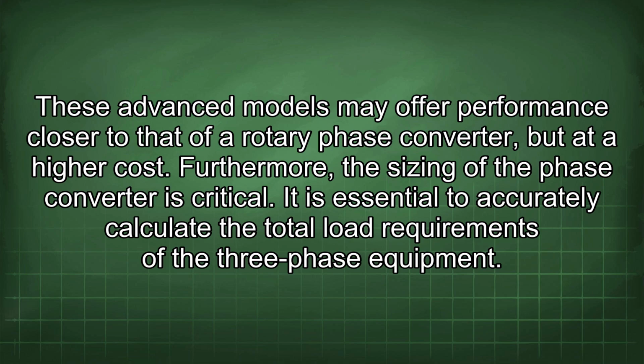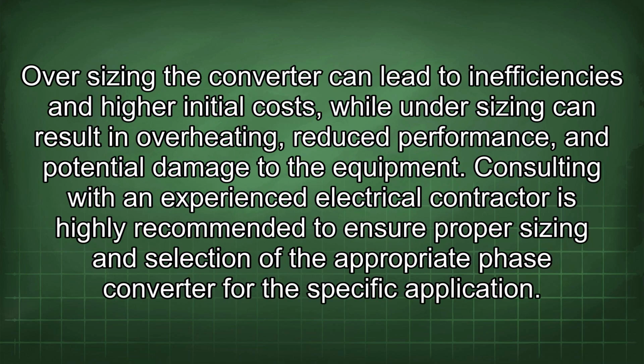Furthermore, the sizing of the phase converter is critical. It is essential to accurately calculate the total load requirements of the three-phase equipment. Oversizing the converter can lead to inefficiencies and higher initial costs, while undersizing can result in overheating, reduced performance, and potential damage to the equipment.